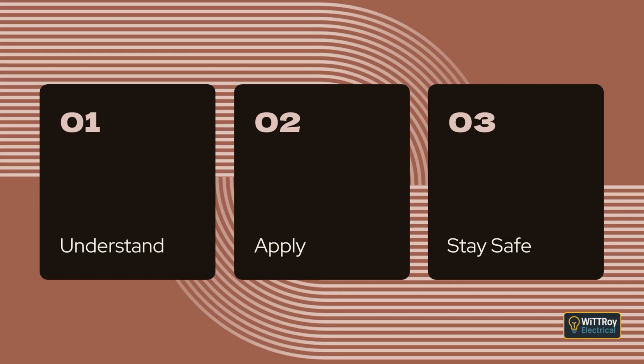The first is hazardous areas formed by gas or vapor where a flammable atmosphere is present or may be present. These areas are divided into zones based on how often and how long the flammable atmosphere is expected, and include vapors arising from liquids. The second type is hazardous areas formed by dust. These areas involve clouds of combustible dust that may be present or may form, and special precautions are needed for installation and use of equipment.